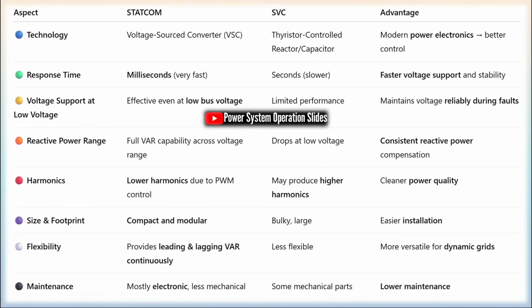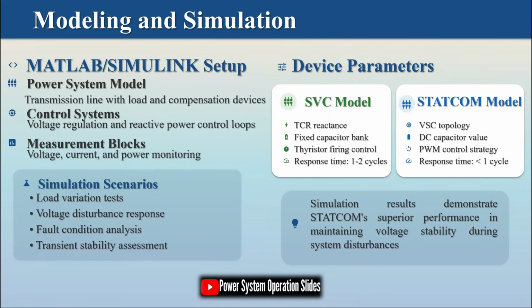Simulation studies using MATLAB/Simulink have demonstrated the superior performance of STATCOMs in various scenarios, including load variations, voltage disturbances, and fault conditions. These studies show that STATCOMs provide better voltage regulation, faster response to system changes, and improved transient stability compared to SVCs. The voltage-independent characteristic of STATCOMs is particularly valuable during severe voltage dips, where they can maintain full reactive current support while SVC capability is significantly reduced.